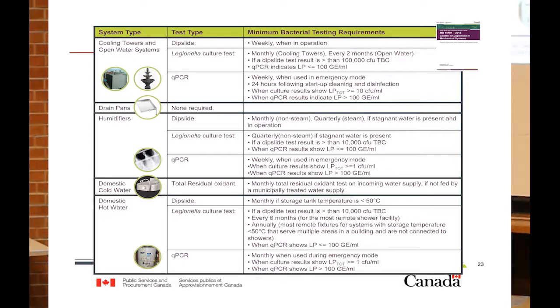That's why we go with qPCR testing right at the beginning of startup, so that we have confidence that we are operating in a clean and sanitary state. However, because qPCR can detect living and dead Legionella, it is always followed up by a Legionella culture test to validate whether there is any living Legionella in the system.